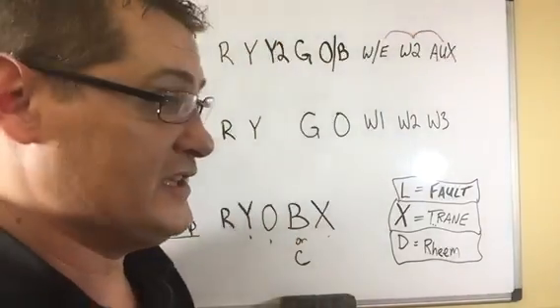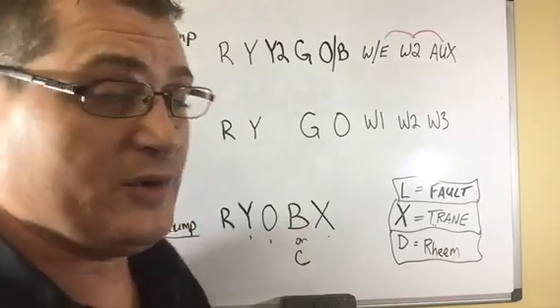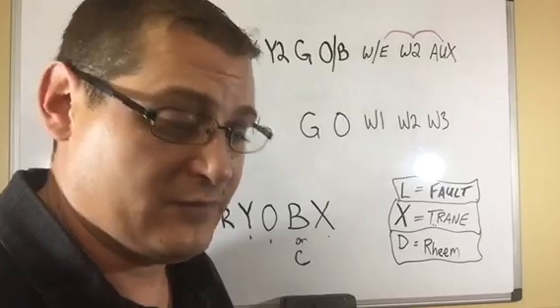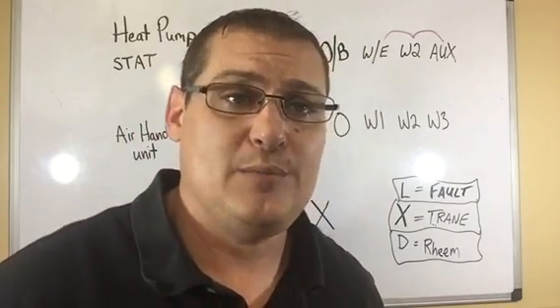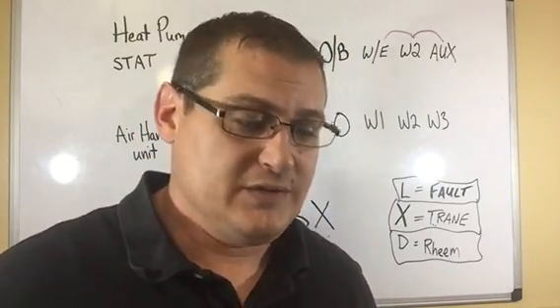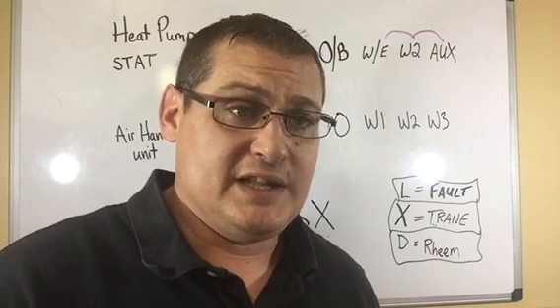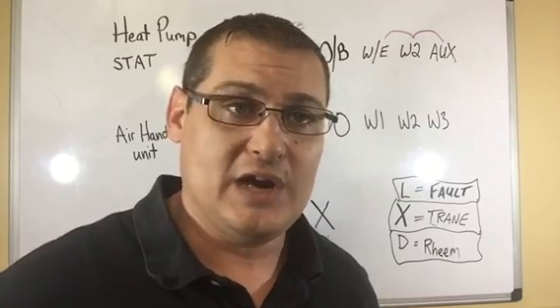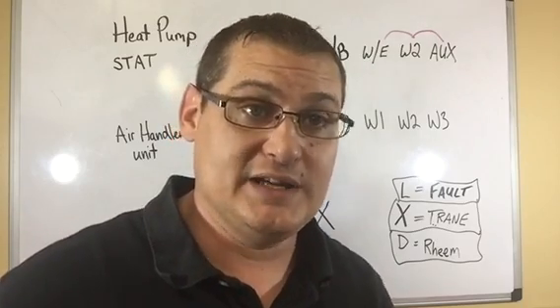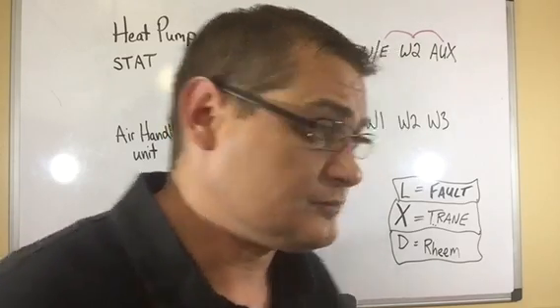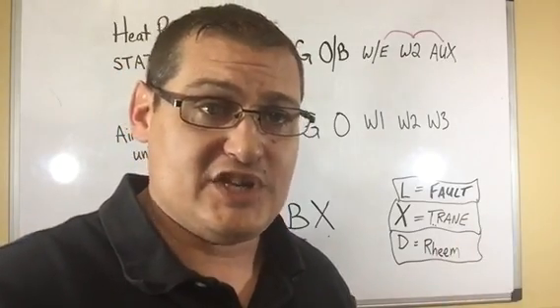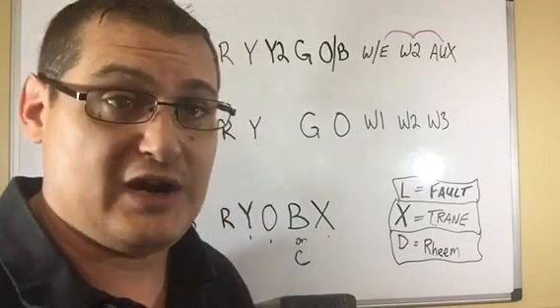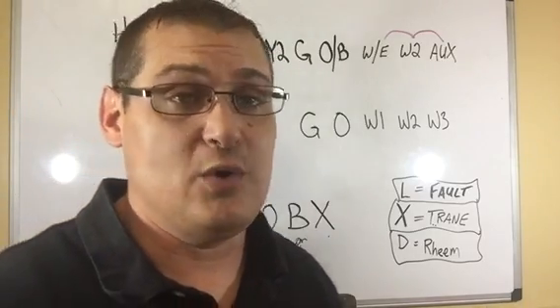Anytime you're hooking up a heat pump, I would always glance over the instructions that come with the thermostat and the instructions that come with the air handler. The air handler will have a layout of exactly how to wire the thing for that particular brand, make, and model. You just got to pick the right combination. It may have several different options in there. As long as you pick the right model, you'll wire it exactly how the system says. I always recommend that.